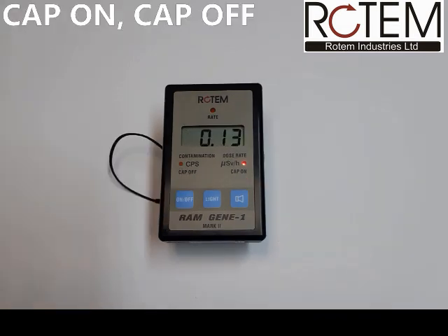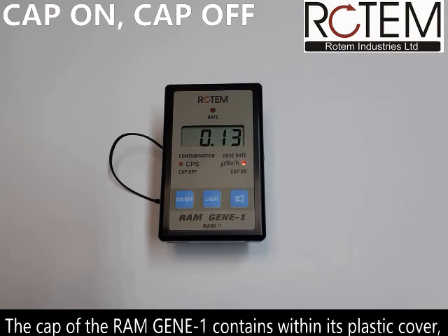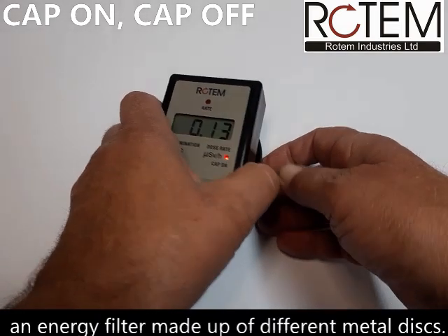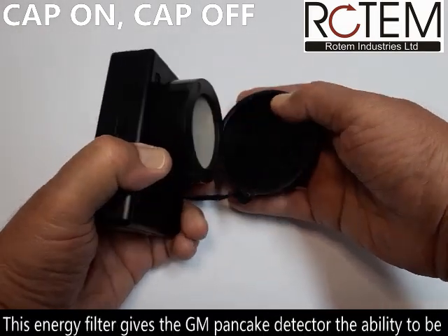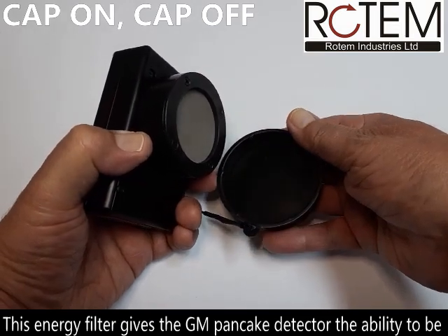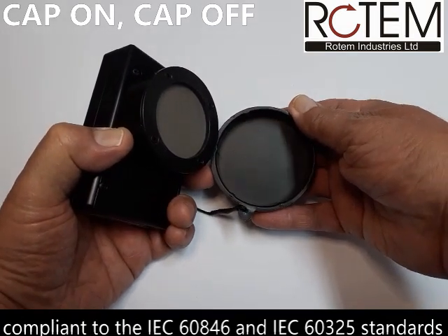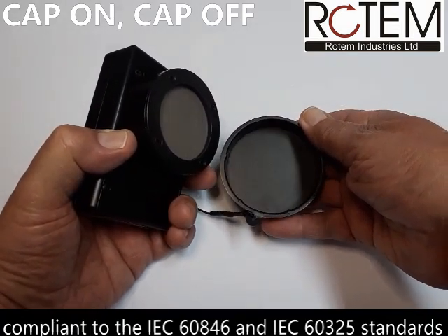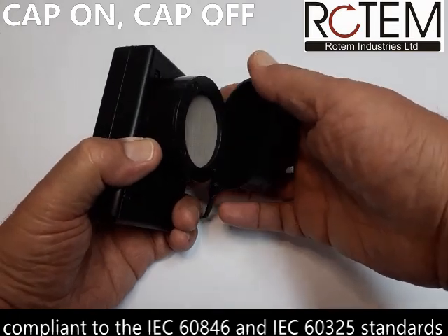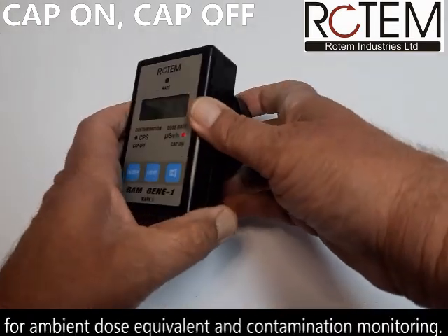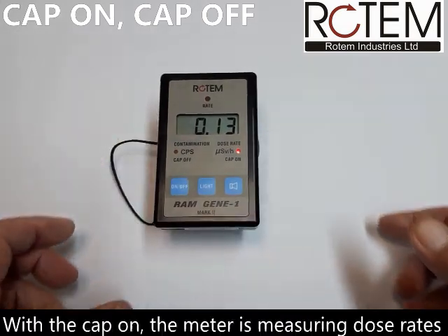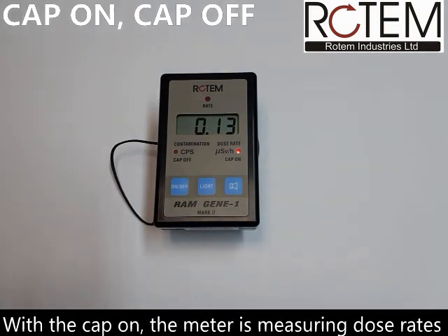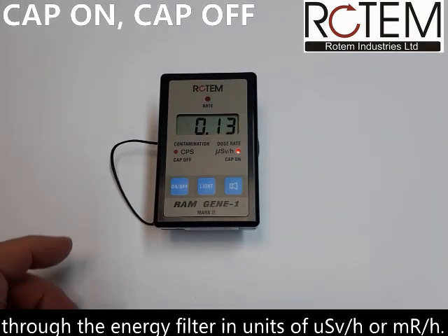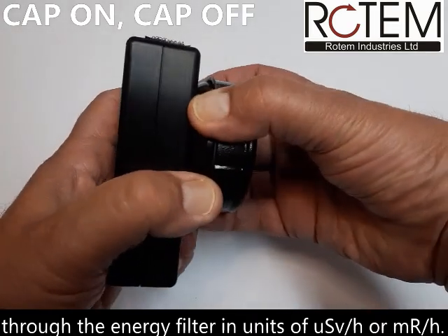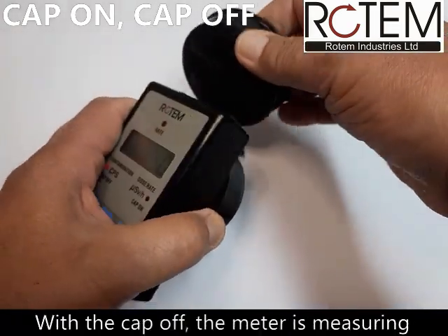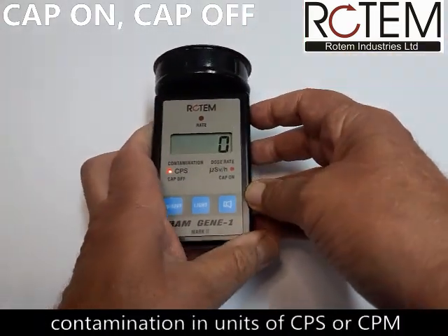Cap on, cap off. The cap of the RAM Gene 1 contains within its plastic cover an energy filter made up of different metal discs. This energy filter gives the GM pancake detector the ability to be compliant to the IEC 60846 and IEC 60325 standards for ambient dose equivalent and contamination monitoring. With the cap on, the meter is measuring dose rates through the energy filter in units of microsieverts per hour or milliroentgen per hour. With the cap off, the meter is measuring contamination in units of counts per second or counts per minute.